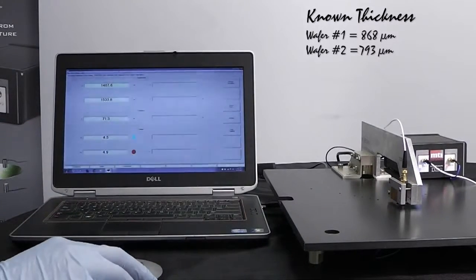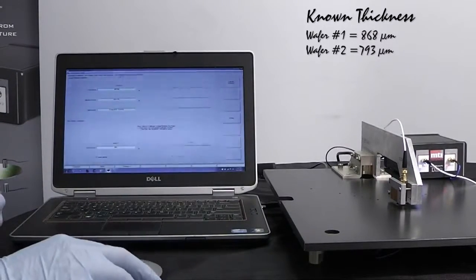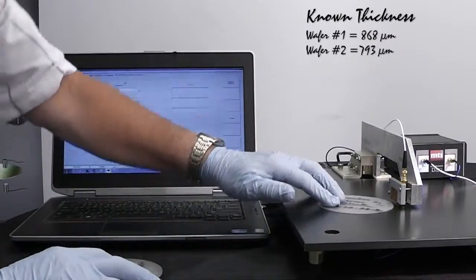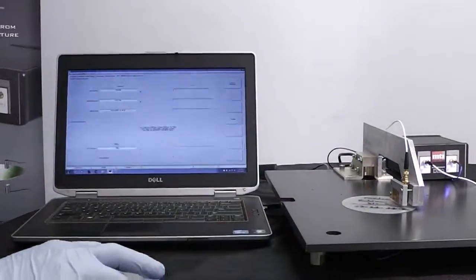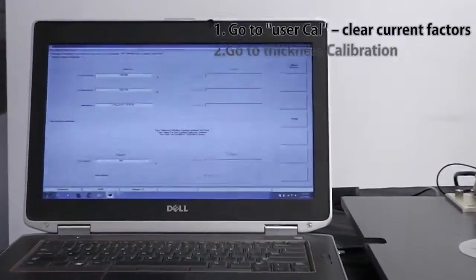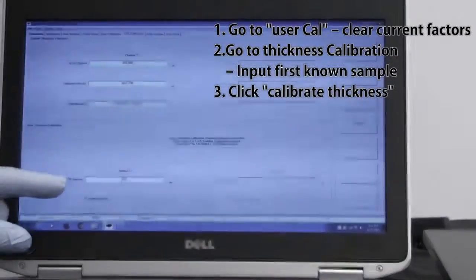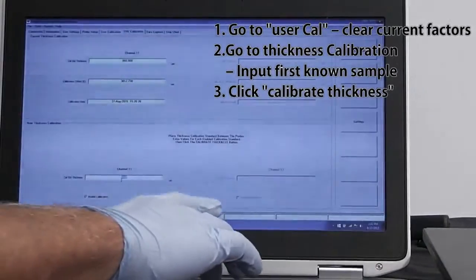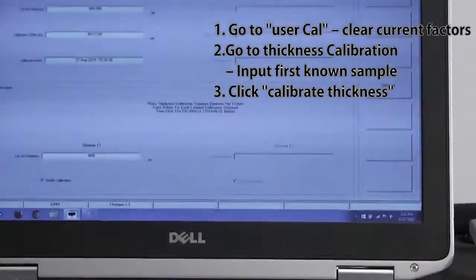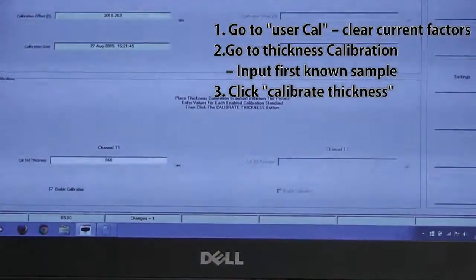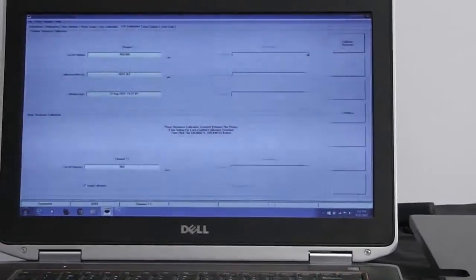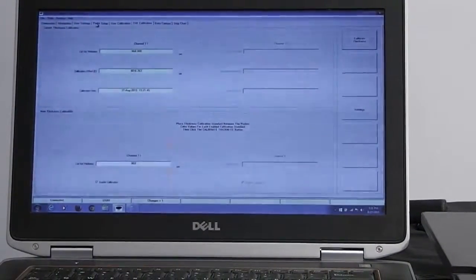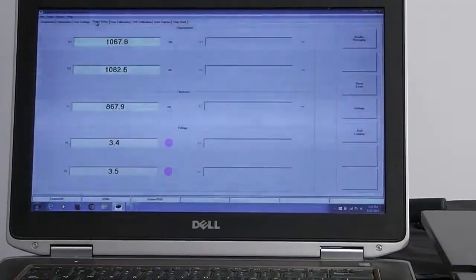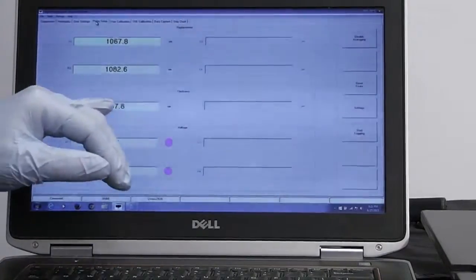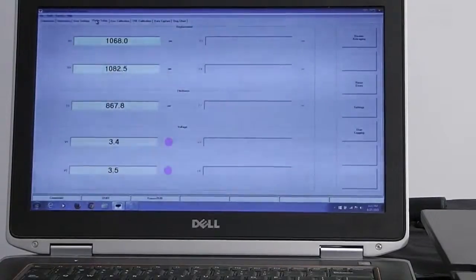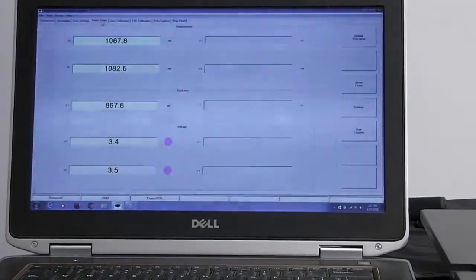The next thing we're going to do is go to the thickness calibration tab. We're going to slide our wafer under between the probes, right where the known thickness area is. We put the thickness in our calibration standard thickness window, 868 microns, and then I click calibrate thickness. So now we've got the probe offset in there for the first wafer. We can go back and double check. It's 868 point something. It's coming out 867 here. It's close enough for this demonstration purpose at this point.